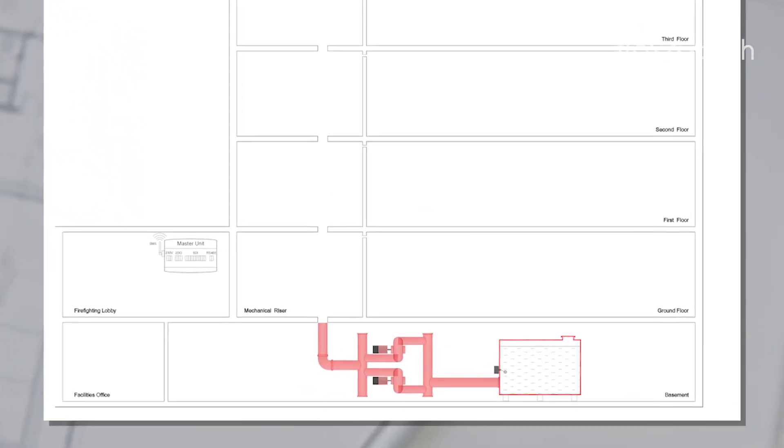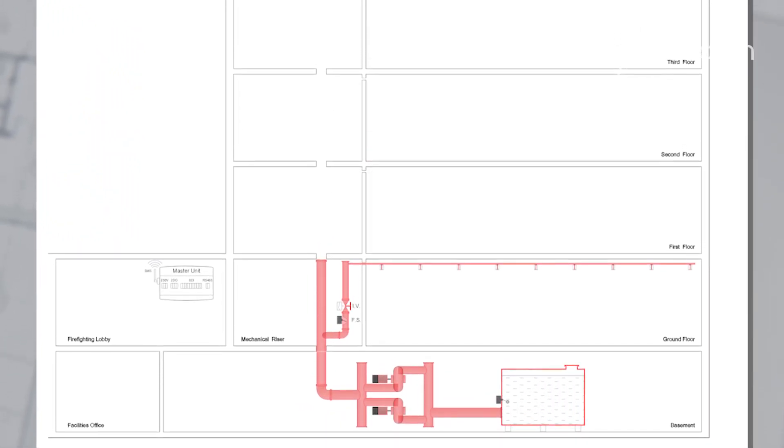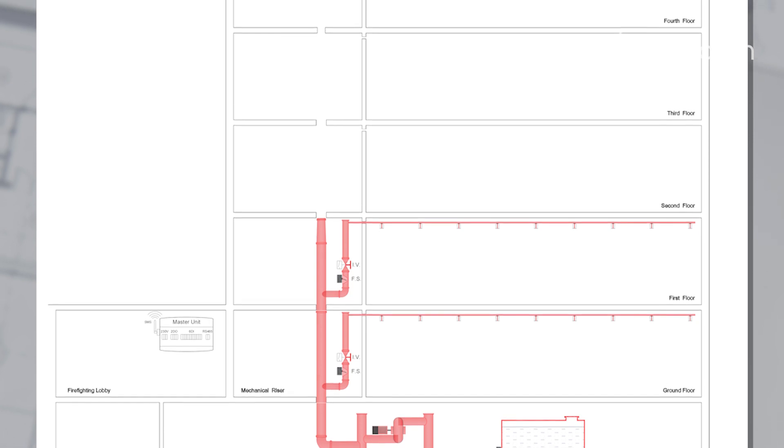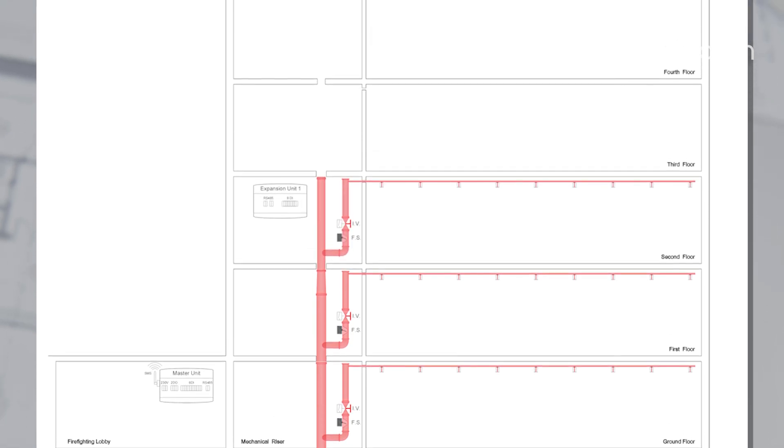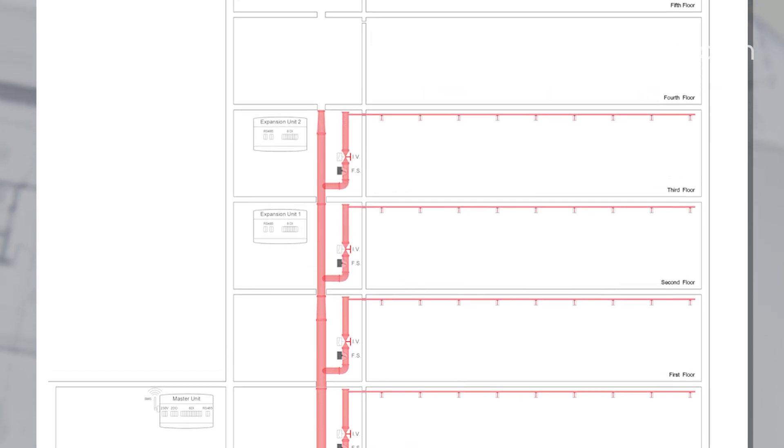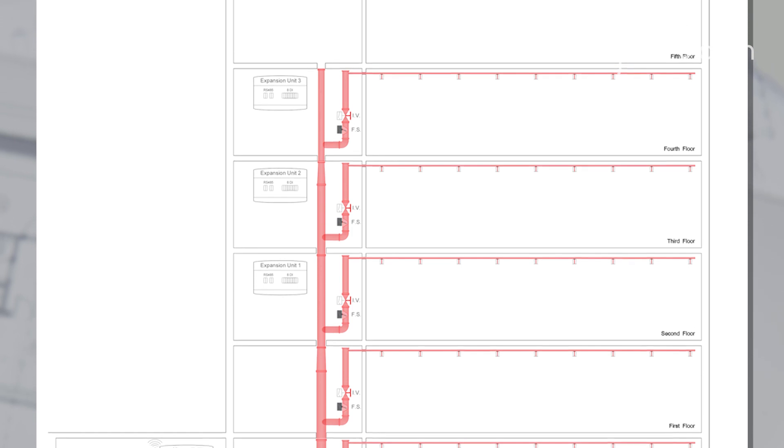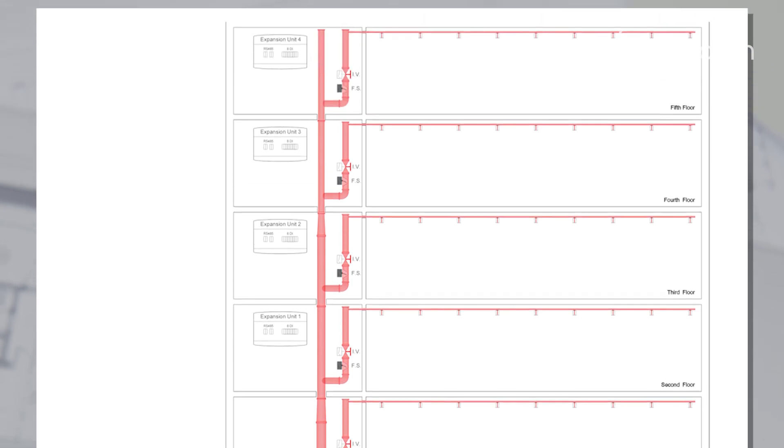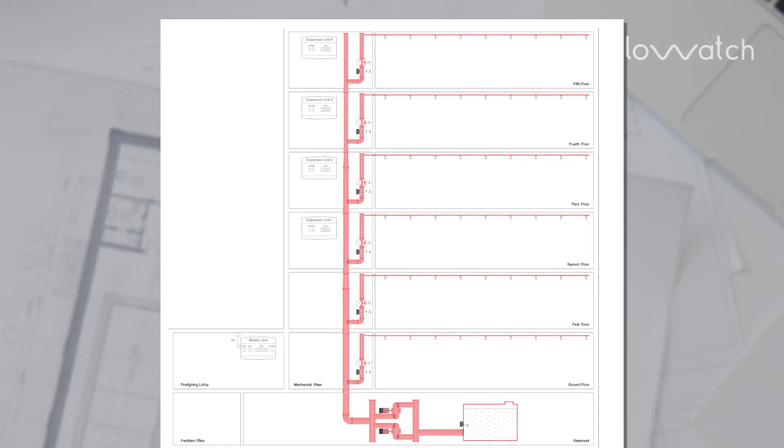Wiring diagrams will be engineered by our design team on order placement. Locations vary dependent on system configuration, i.e., number of floors and number of inputs required. From the master panel, a four-core FP 200 1 millimeter cable should be installed to the first expansion module.